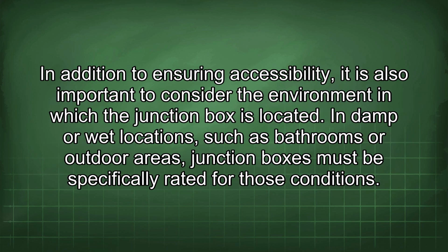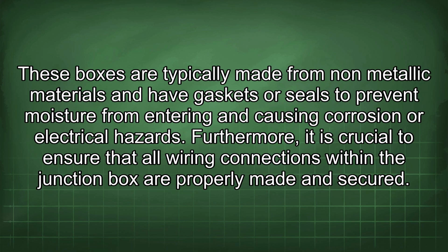In addition to ensuring accessibility, it is also important to consider the environment in which the junction box is located. In damp or wet locations, such as bathrooms or outdoor areas, junction boxes must be specifically rated for those conditions. These boxes are typically made from non-metallic materials and have gaskets or seals to prevent moisture from entering and causing corrosion or electrical hazards.